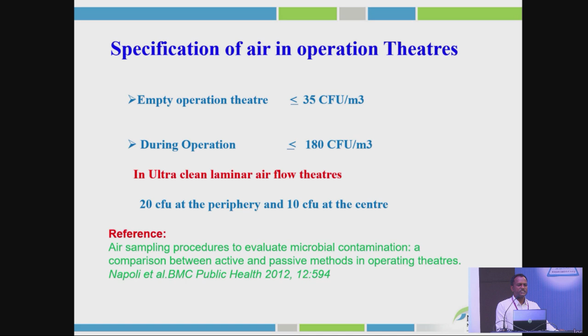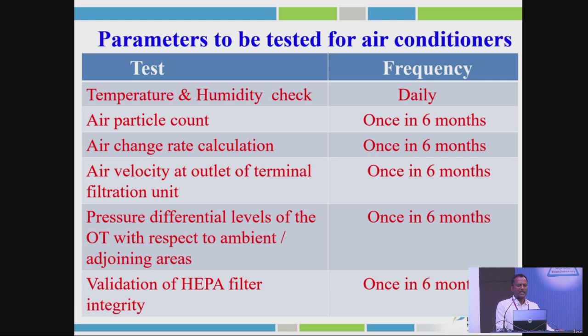Apart from surveillance of OT, you need to check the parameters to be tested for air conditioners. First is temperature and humidity check daily, air particle count once in 6 months, air change rate calculation once in 6 months, air velocity at the outlet of terminal filtration unit once in 6 months, and pressure differential levels of the OT with respect to ambient adjoining areas once in 6 months. Validation of HEPA filters and integrity is also once in 6 months.